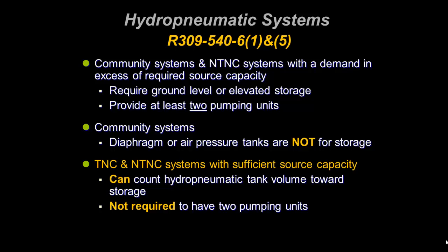So for community drinking water systems, hydropneumatic tanks cannot be counted towards the required storage volume. For transient and non-transient non-community systems with sufficient source capacity, they can count these types of tanks toward their storage requirements. They also are not required to provide redundancy in pumping.